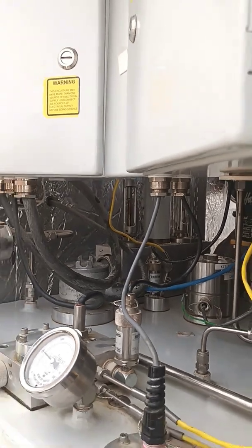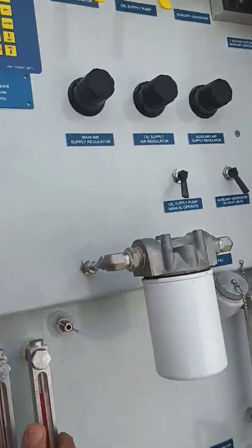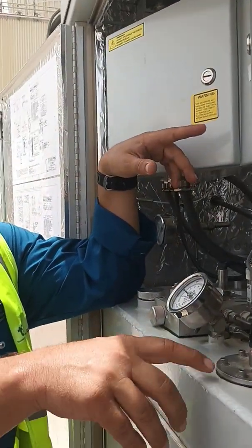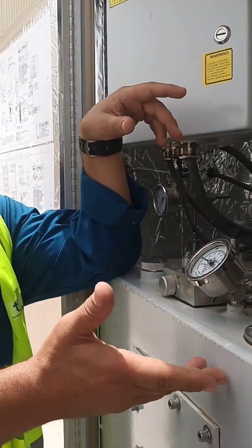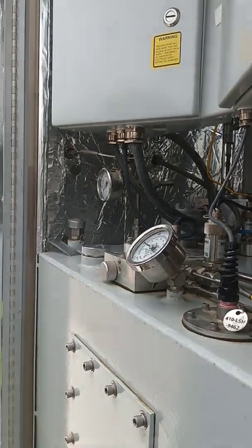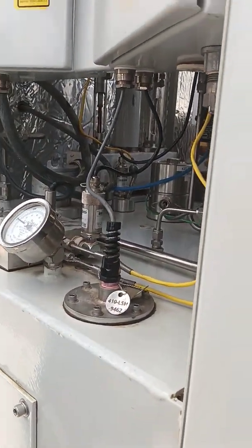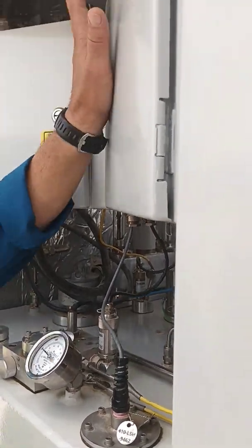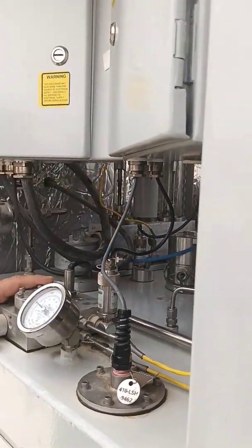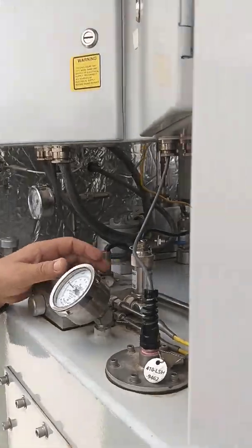So this is what is keeping the oil level in this tank. This is what is controlling that pump. Every time the level is asking to make up, it will open the air for the pump, which is controlled with a solenoid valve. So this is basically opening and closing a solenoid valve, which is on the backside of this box. There you have a solenoid valve with a gauge. That gauge is the pressure that is going to the pump.